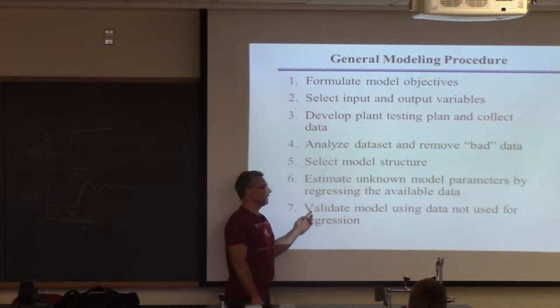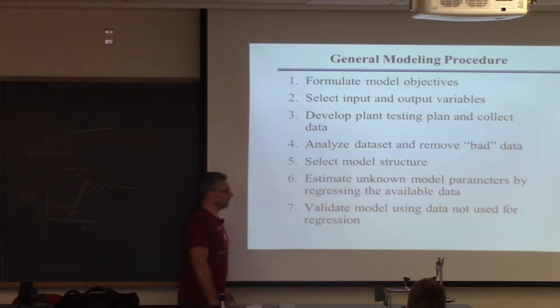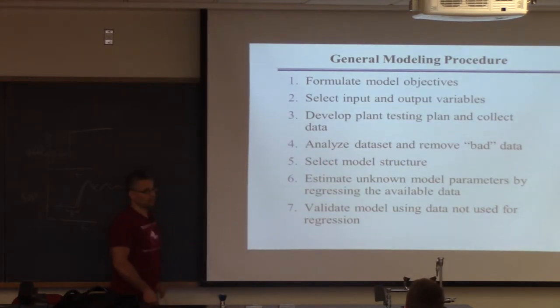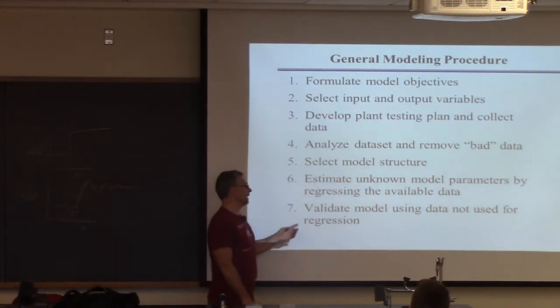The thing about modeling is if I give you a reasonable model, I can fit it to an individual data set unless it's a really bad choice. It doesn't mean it's going to work for other data sets. If this model only works for this step change, that's a problem. Because what happens if you want to decrease the reflux? Then the model's no good. And if the model's no good, the controller won't work that you design from it.